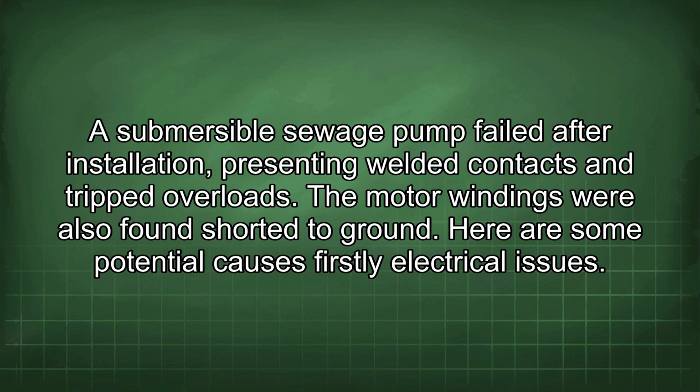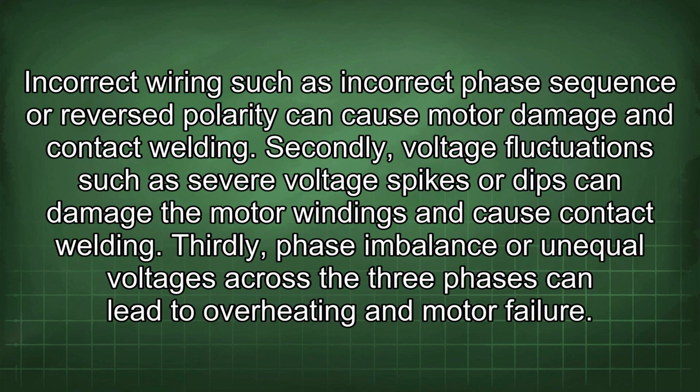Firstly, electrical issues. Incorrect wiring, such as incorrect phase sequence or reverse polarity, can cause motor damage and contact welding. Secondly, voltage fluctuations, such as severe voltage spikes or dips, can damage the motor windings and cause contact welding. Thirdly, phase imbalance, or unequal voltages across the three phases, can lead to overheating and motor failure.